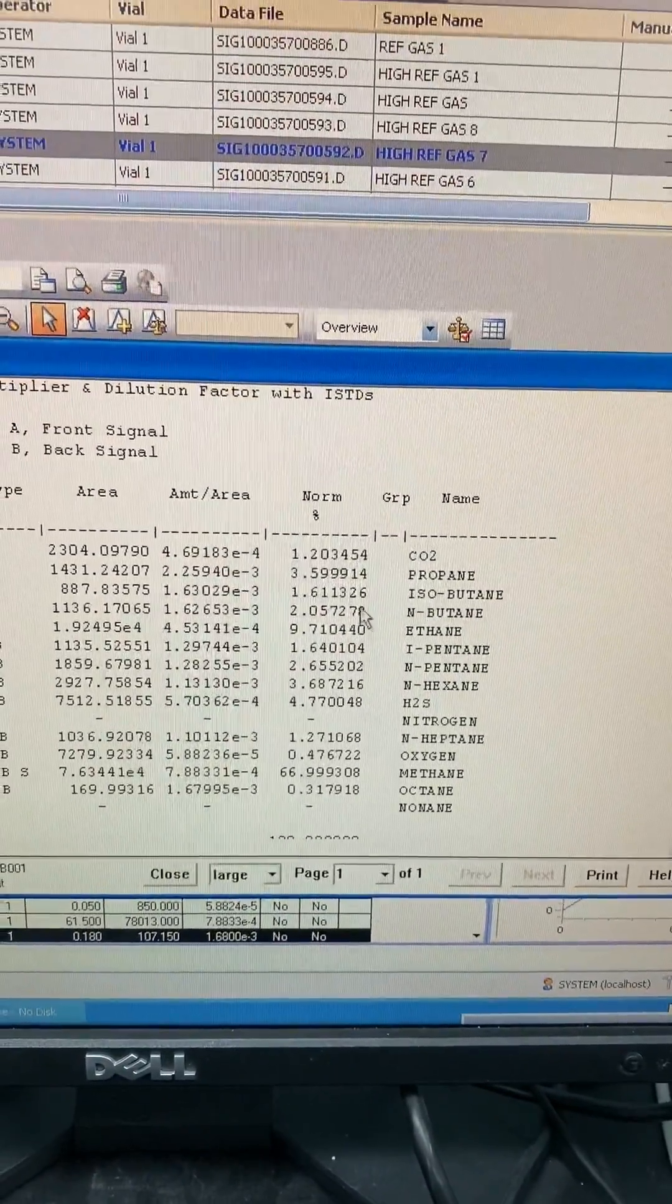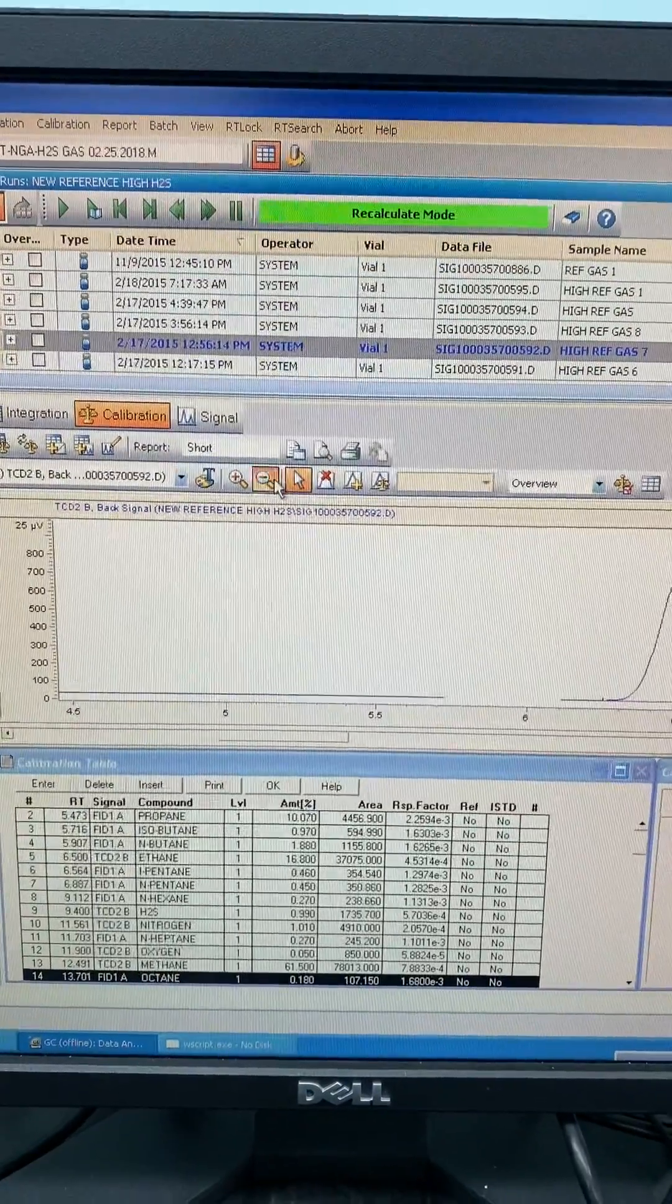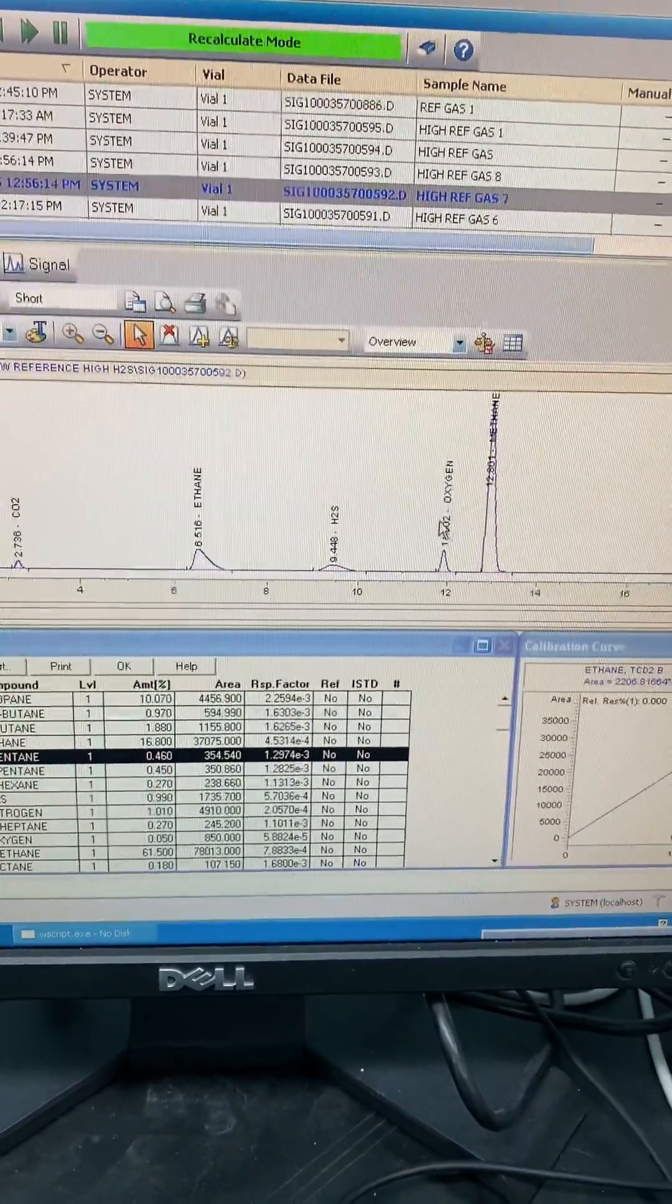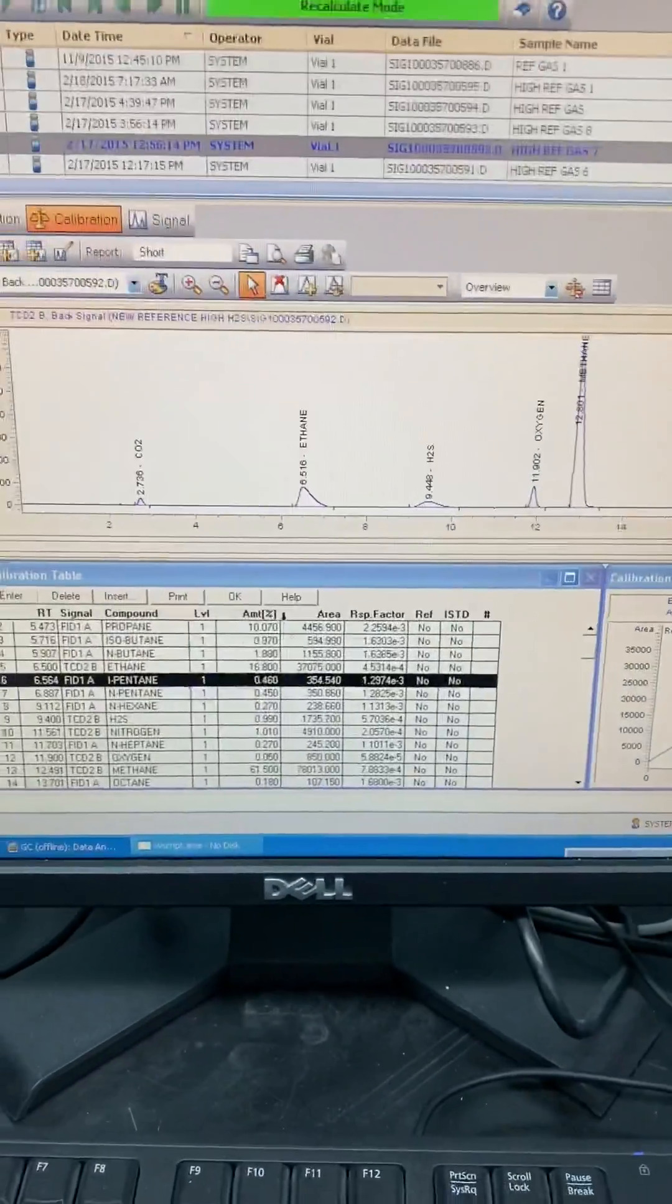Let's open again the report and see. We have already changed the retention time. So that means all of the peaks are already identified except nitrogen and nonane. Let's open again TCD. See? In this case, there is no nitrogen eluted. That means I have two reasons. Either there is no nitrogen in this reference material that been injected to the GC, or the concentration was very low and was not detected here. So if you have another peak, you can name it as nitrogen and then you will see the result are there.